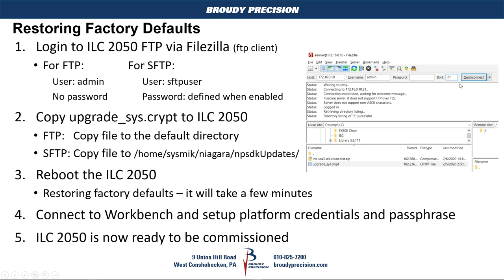The FTP port is 21. Once you log in with FTP, you'll find only one root directory with no subfolders — that is where you copy the .crypt file. If you've enabled SFTP, you'll find various folders on the controller side, and the file gets copied to home/sysmik/niagara/npsdk/updates folder. Once you've copied the file over to the ILC 2050, do a reboot: go back into PuTTY, select reboot from the menu, and allow it to reboot.